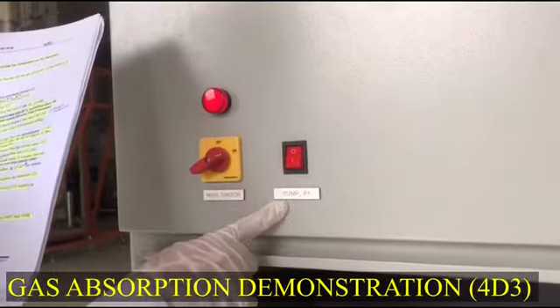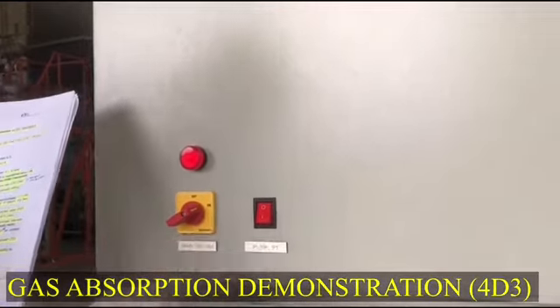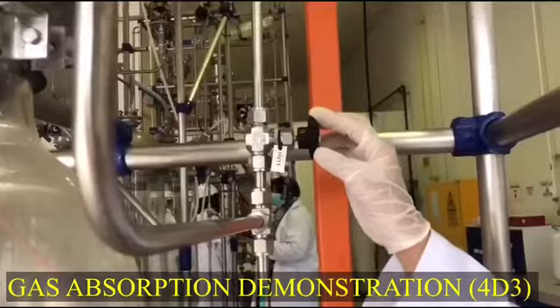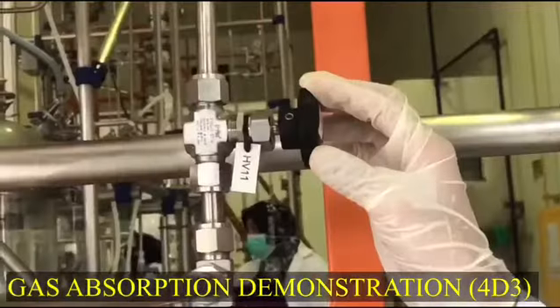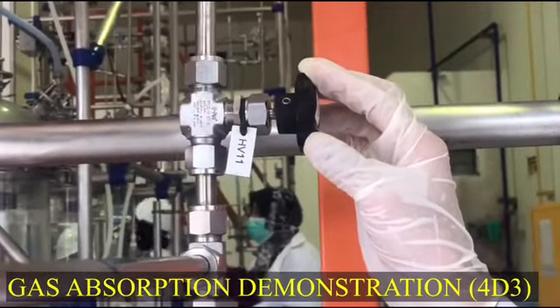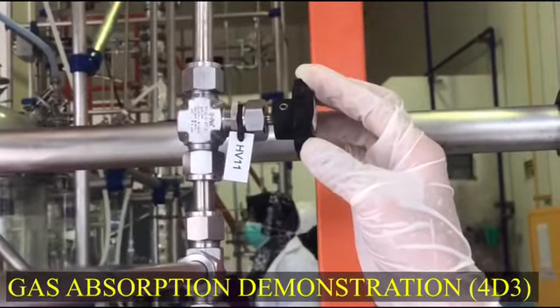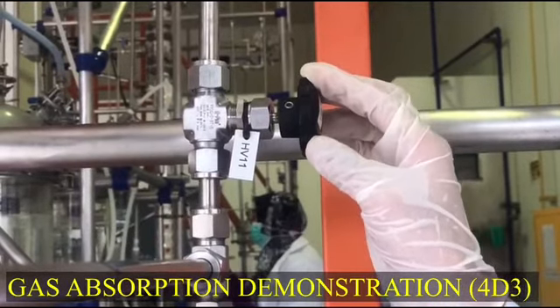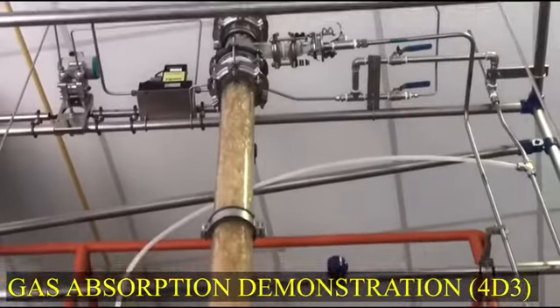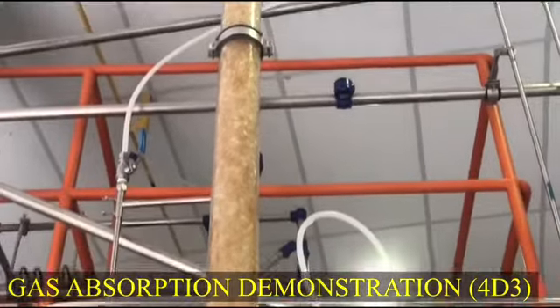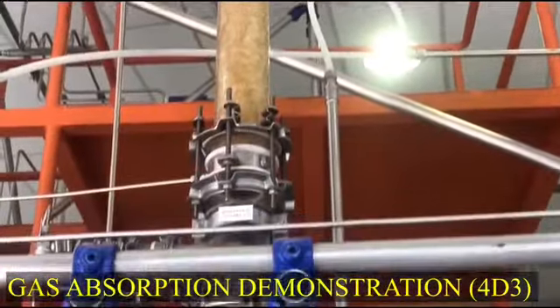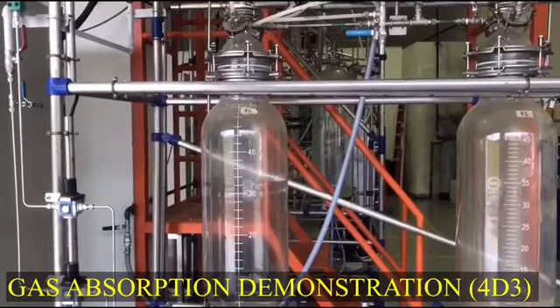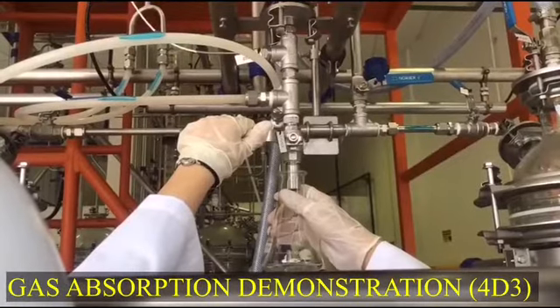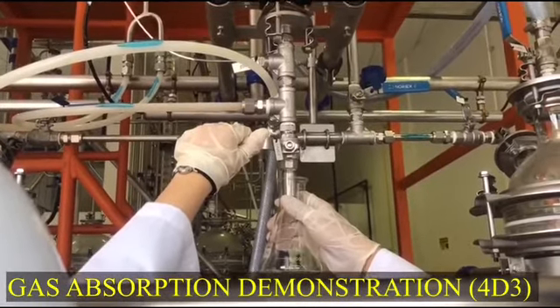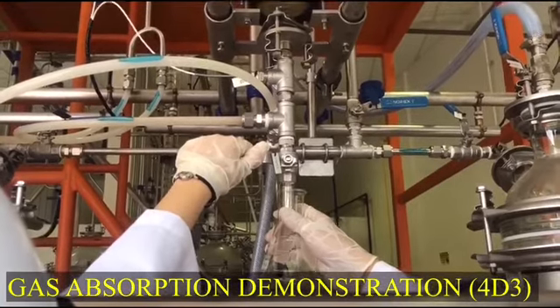Turn on pump 1 at control panel. Open and adjust valve HV11 to give a water flow rate of approximately 1.5 litre per minute at FT303 on control panel. Allow water to enter the top of the column K1, flow down the column and overflow back into vessel B2. Collect an initial sample using a 100 ml Erlenmeyer flask by opening valve HV03.